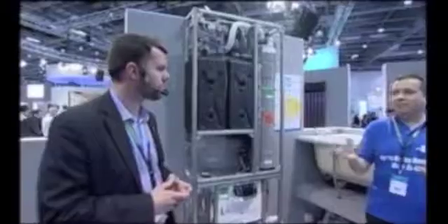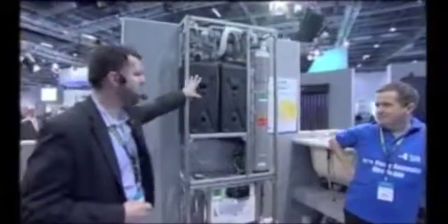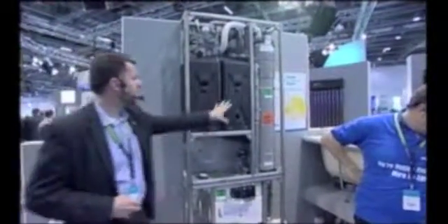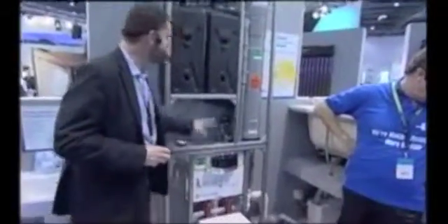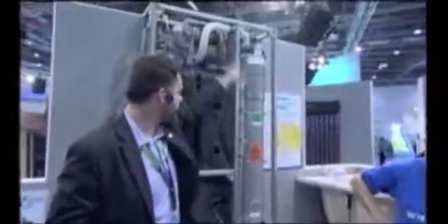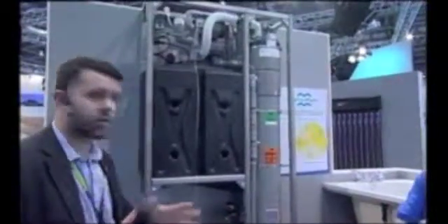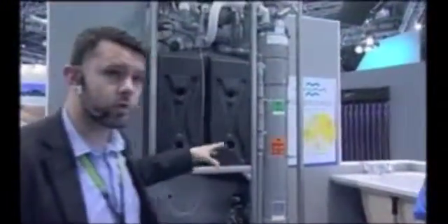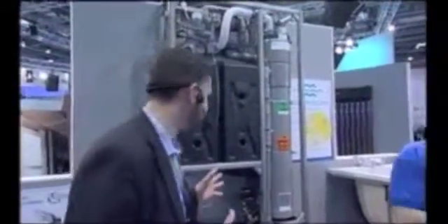So, how does it actually work? Basically, the top half of the system is where all the processing occurs. You have a clean tank on the right hand side — this is the storage tank — and then the system on the bottom. Water comes in from the bath or shower at the top, comes into the tank on the right hand side, and basically there is a two-stage process: separation and disinfection. Any of the larger deposits — sand, grit, dirt, etc. — sink to the bottom of the tank; any lighter deposits actually rise to the top and are skimmed off. We also inject a small quantity of disinfectant into the water to keep it cleaner for longer and to increase the stagnation point.